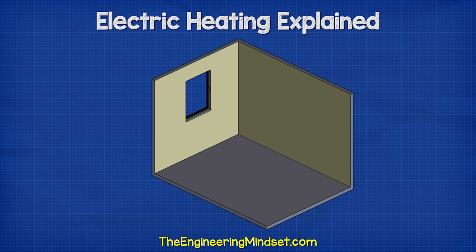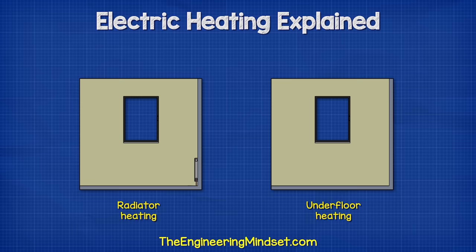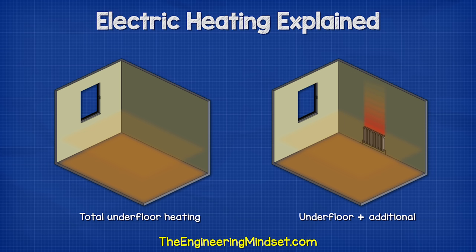Ordinarily, we might find a forced air heating vent or a single radiator on one of the walls, which is either electric, hot water, or steam heated. This will be a high temperature, as it has a relatively small surface area. Hot air rises, so this leads to poor thermal distribution and also poor thermal comfort within the room. Compare this to underfloor heating and we see it's more evenly distributed. We can have either total underfloor heating, or we can combine this with an additional heat source for those extremely cold winter days.